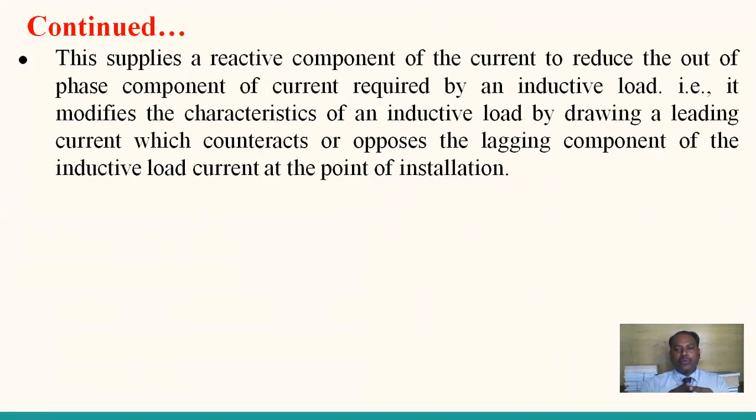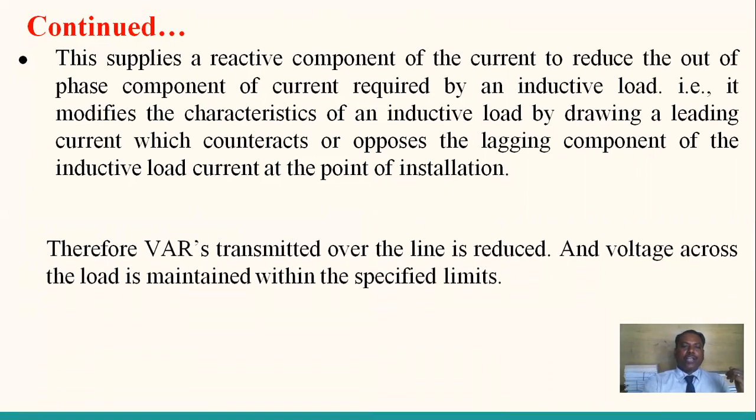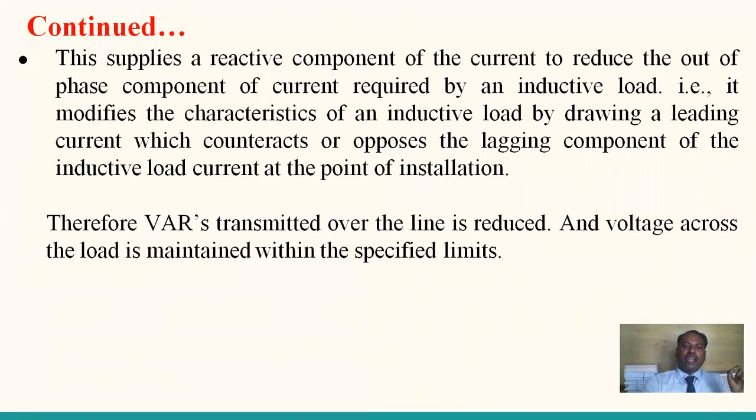Therefore, the angle between voltage and current is reduced, and obviously the power factor increases. So the volt ampere reactive, the reactive power transmitted over the line, is reduced, and the voltage across the load is maintained within the specified limits.